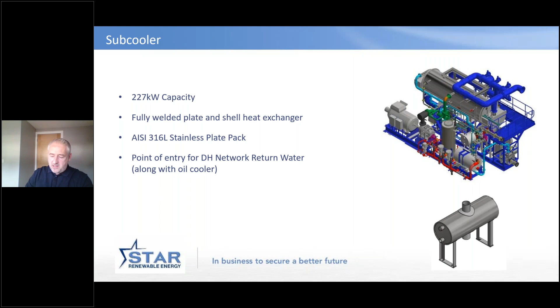But the biggest bit is if we can widen the delta of the network, we get a better efficiency. And that's really what we're trying to do here, and I'll try and show exactly why. But equally, the oil cooler is about 600 kilowatts out of 2.6. So that's a big area of heat recovery.